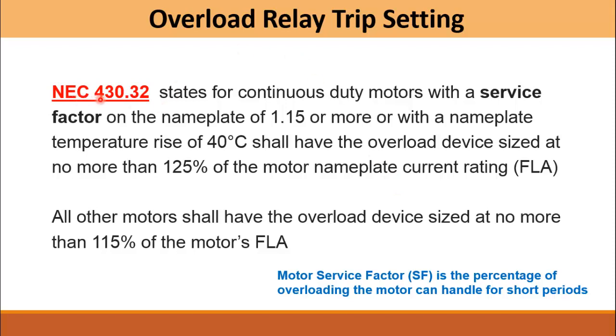According to NEC clause 430.32, for continuous duty motors with a service factor on the nameplate of 1.15 or more, or with a nameplate temperature rise of 40°C or less, the overload device shall be sized at no more than 125% of the motor's nameplate current rating.